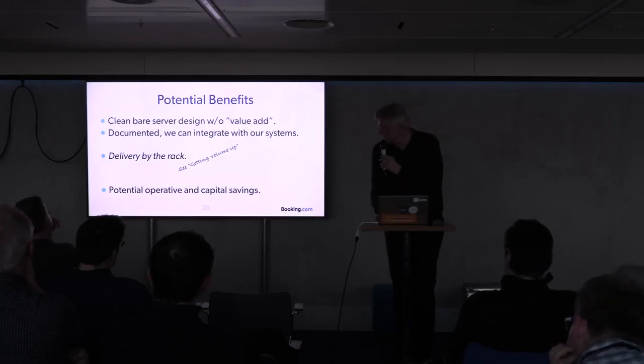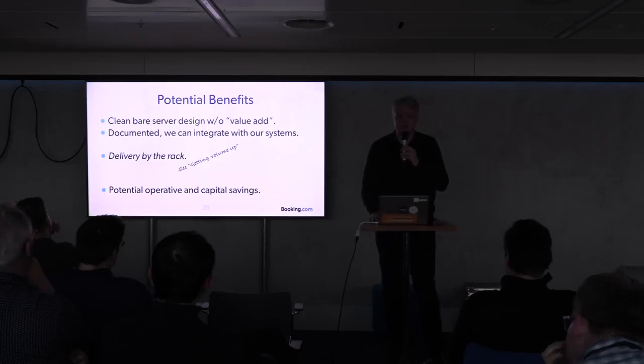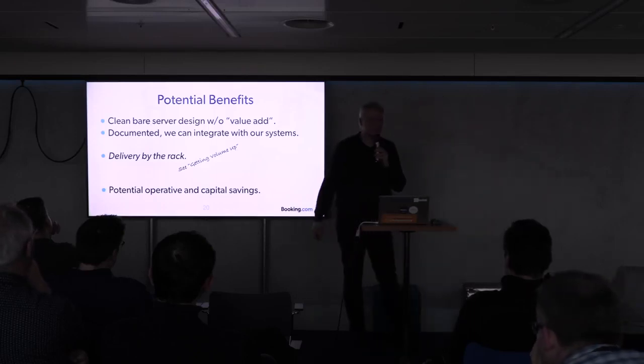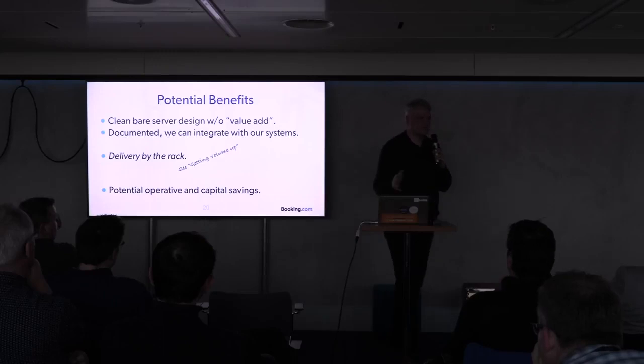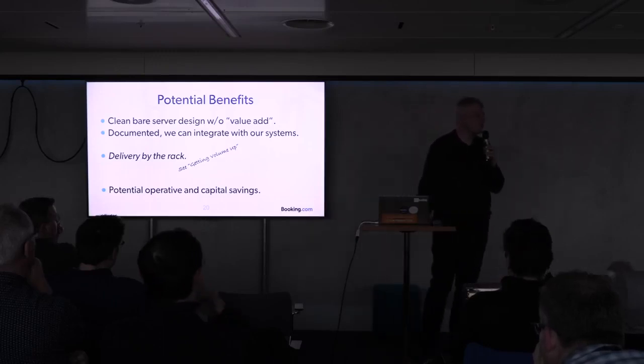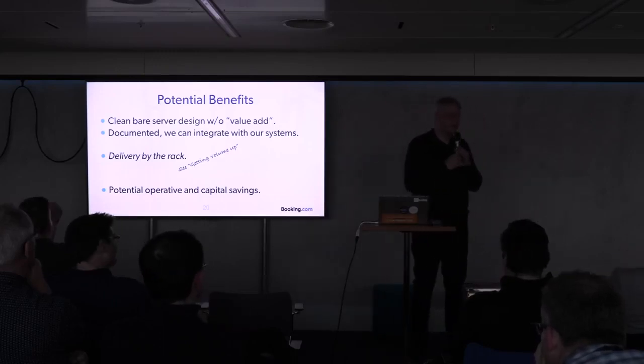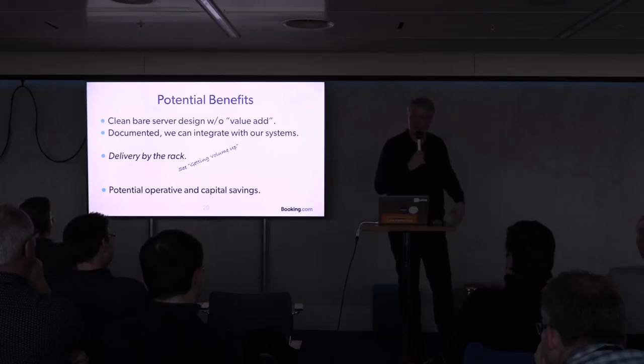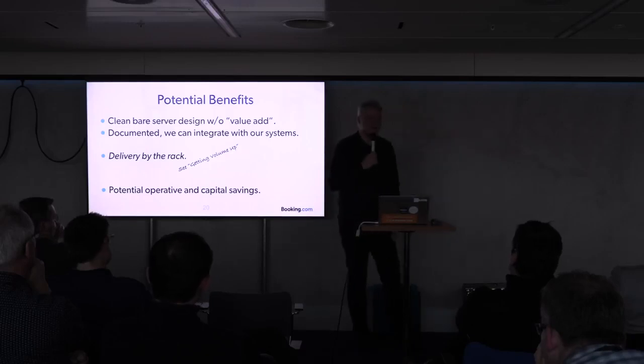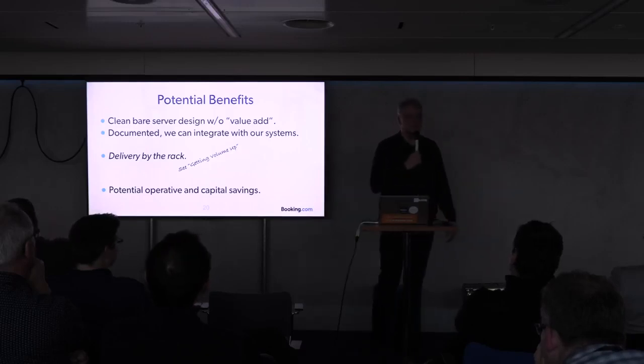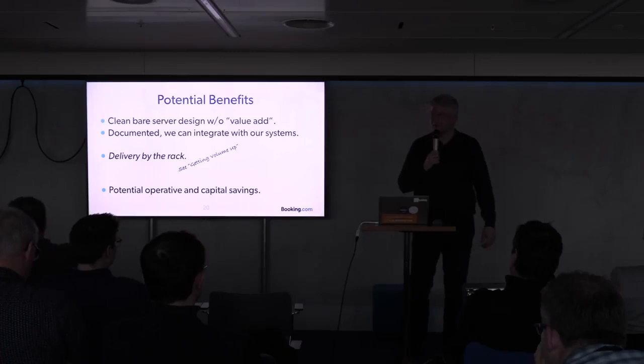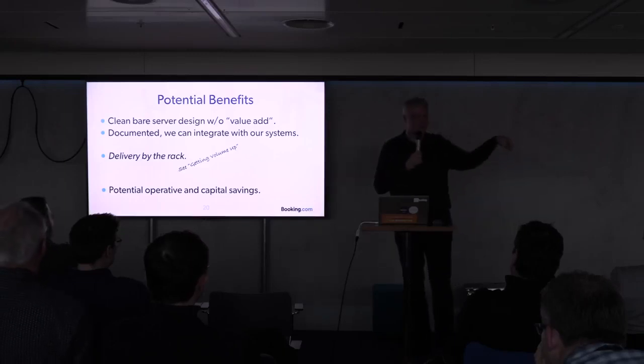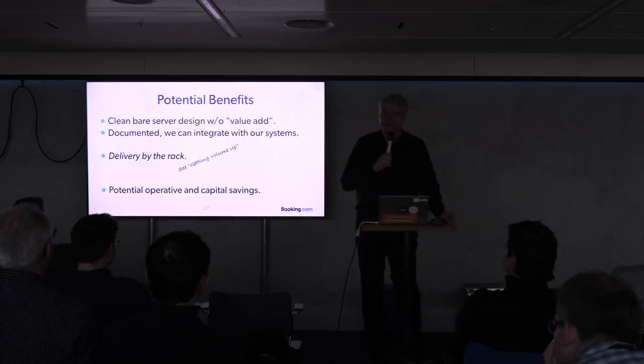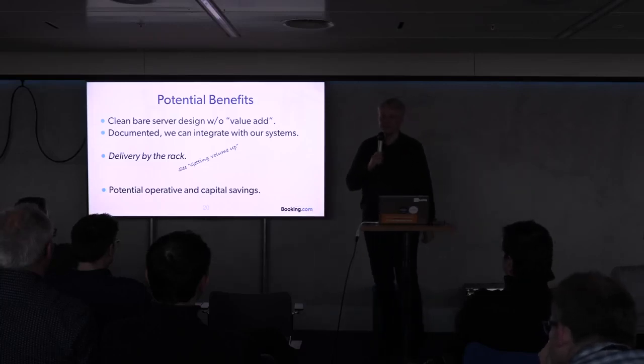The deliveries by the rack — that's a challenge we just mastered for the first time. That was about 670, 680 kilos coming in, and in a traditional colo where we are, that's actually borderline of what's possible. So we're probably not going to get Hadoop hardware by the rack, because on the way to the final location it will break through the floor somewhere, even with spreader plates. 1.5 tons a piece is not going to happen in that location.